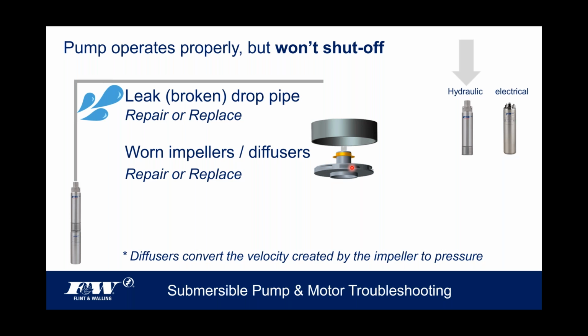All that water coming out of the vanes of that impeller is captured within this diffuser. If we want to know the primary purpose of a diffuser, down at the bottom it tells us: the diffusers are to convert the velocity created by the impeller to pressure. And so when you have a pump that's not building pressure, obviously we probably have something going on in the impeller and diffuser area of that submersible pump.